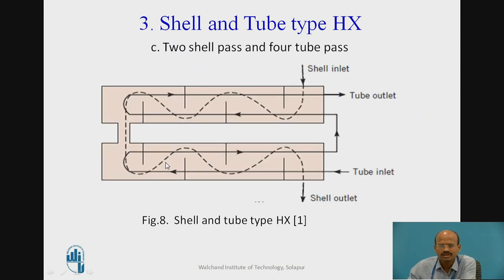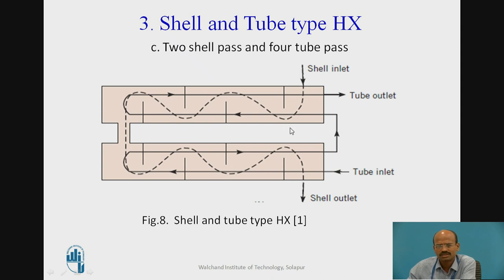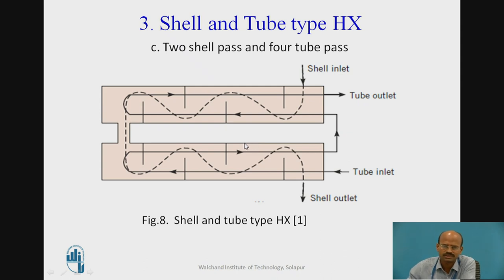We can also increase the number of shells. With two shells, the tube passes become the first, second, third, and fourth tube passes — this is known as two shell passes and four tube passes. If space availability is more, instead of a single shell, we can adopt this two-shell type of heat exchanger.